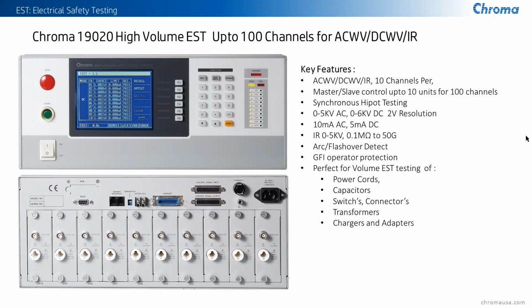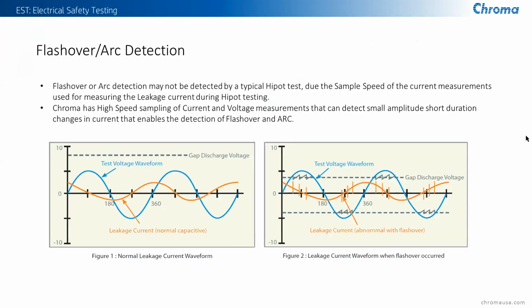These units go all the way up to 6,000 volts DC, 5,000 volts AC. They too have good resolution, 2 volts, 10 milliamps AC, 5 milliamps DC, and insulation resistance up to 50 gigohms. They also include the arc and flashover detect that we're going to cover in just a moment. These are perfect for high volume type testing. Anything from power cords, capacitors, switches, connectors can be done in high volume with these products.